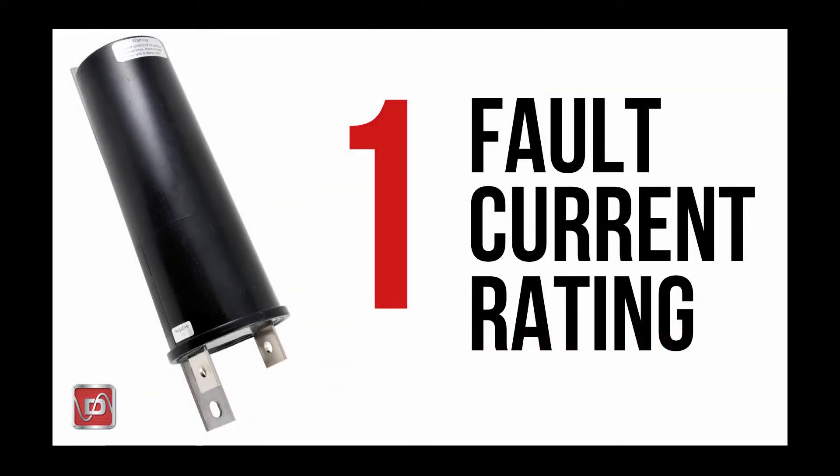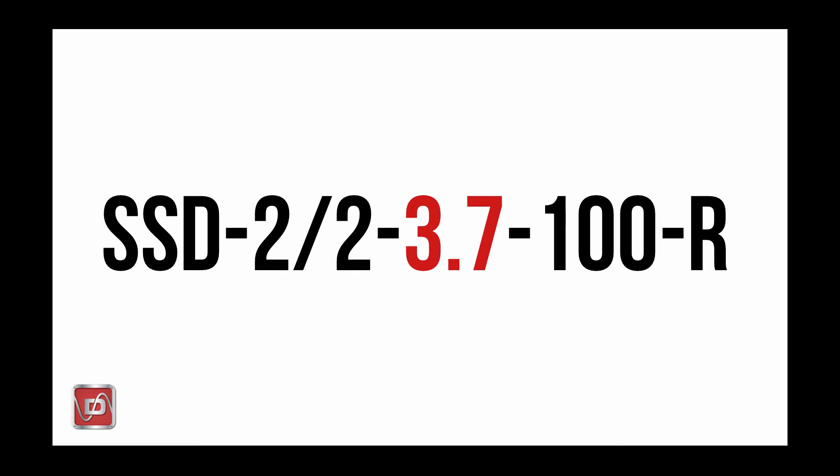Perhaps the most important component to the model number for any of our products is the AC fault current rating. This rating is stated clearly as part of the model number for all of our products and will be stated in kiloamps or thousands of AC amps. This rating relates to the AC fault current exposure for a given application. Every Dairyland product has a stated AC fault rating even if some applications have small or no exposure to AC faults. You'll see this rating designated as a 3.7ka or 10ka or something similar in the part number.